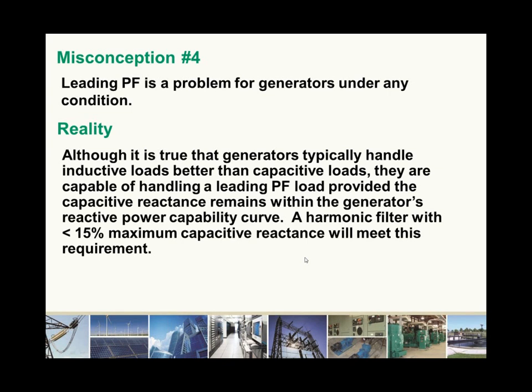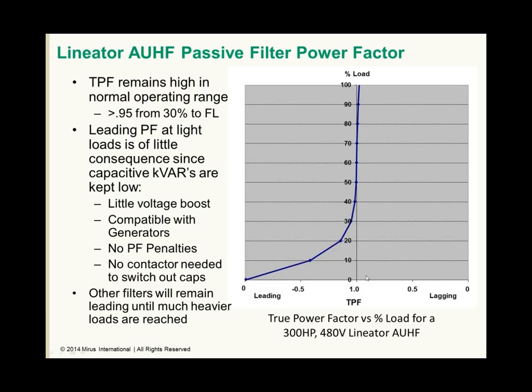I also show the power factor of these passive filters. Here again we have loading on the y-axis. We have leading power factor on the left side, lagging power factor on the right side. Total power factor remains high for our Lineator filter in the operating range, 0.95 or greater, at 30% load and higher. So we're actually typically approaching even 20% loading levels and we're above the 0.95 power factor. We are leading under lightly loaded conditions, but then we end up being lagging as we reach 50% load and up into the higher loading levels.